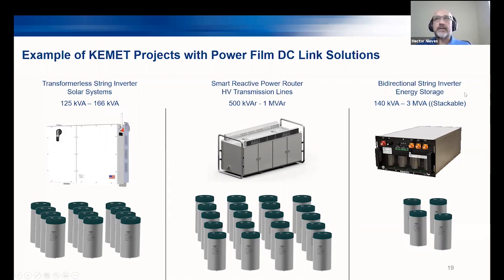And this is another example, an energy storage inverter situation, with the capacitor internal there being bi-directional. It could charge the battery, or it could use the battery energy to produce power factor correction at the same time as producing energy to the grid. These technologies range from levels of hundreds of kVA to levels of megawatts - that's where you see mostly this technology from KEMET.